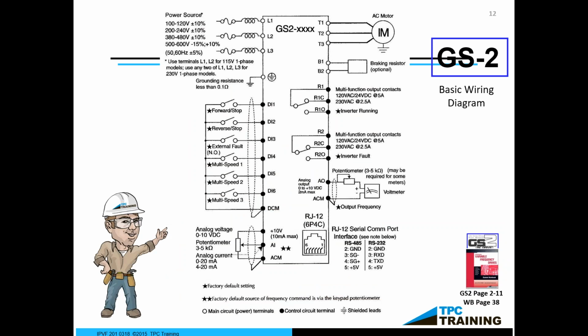One of the last things I want to talk about is how to wire one of these little rascals up. Not difficult, but we have to understand what our digital inputs are. Do you see the DI1, DI2, DI3, DI4? Those are digital inputs. There in the lower left, it's AI. Those are analog inputs. The majority of your analog inputs are going to be a 4 to 20 or a 0 to 10 volt signal. You've got to determine it. We can select which one of those signals we want, depending on the application.